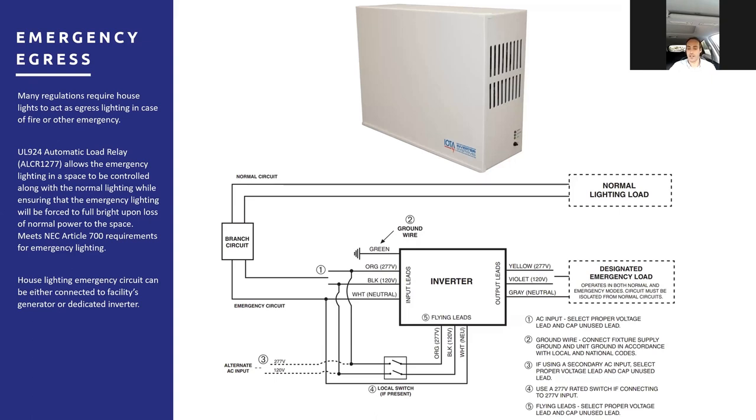With places of high concentration, 50 people or more typically, regular emergency lights that are built into fixtures or that are mounted externally are not going to give enough brightness to force a mass evacuation in a short amount of time. So code now for new construction, a lot of states, I know I have different contacts here from different states, so we're just focusing on the UL, not exact state guidance. But at least I know where we are in New Jersey, it is a requirement to comply for all new theatrical lighting systems. So just ensure that the new system has capability to accept a fire alarm or an emergency signal and switch over. Tie in, a lot of times, to emergency backup or UPS is done separately, or it could be worked into the design.